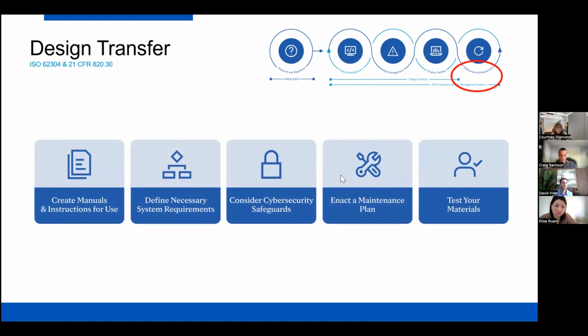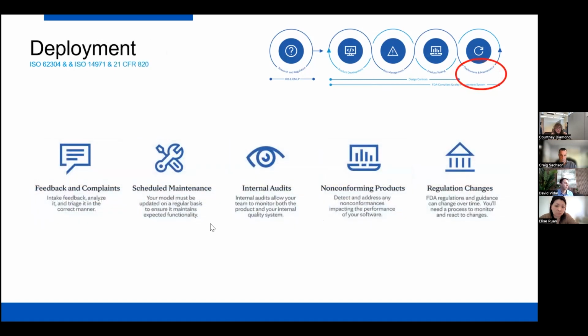Of course, we have security, we have our continuous maintenance plans, system maintenance plans, and then we actually have to test these as well. So part of the testing that we would submit to the FDA would be to make sure that we can actually take this product and transfer it into clinical practice. And then lastly, we have our post-deployment. So these are mostly grouped under the category of quality management systems regulation. So less about, although related to, design controls. And that would be formal systems to make sure that we have feedback, maintenance, audits, that we know how to handle and what to do if we identify a product that's not working, and then we have actions to make sure that we're adapting to the regulations.